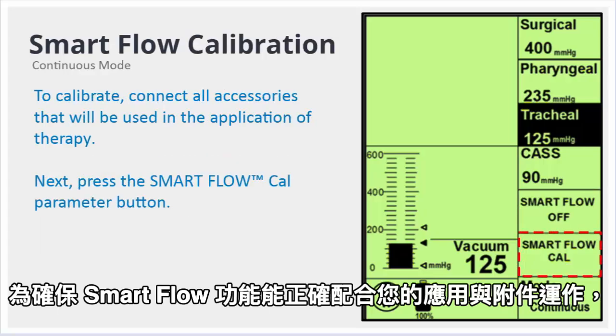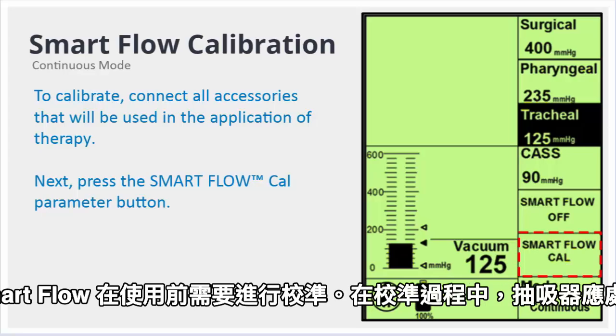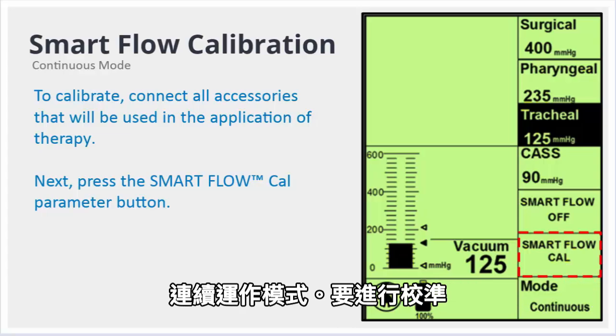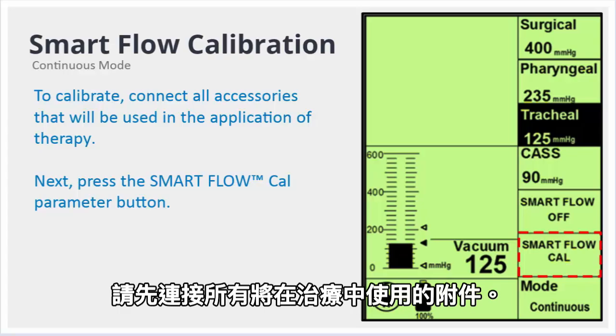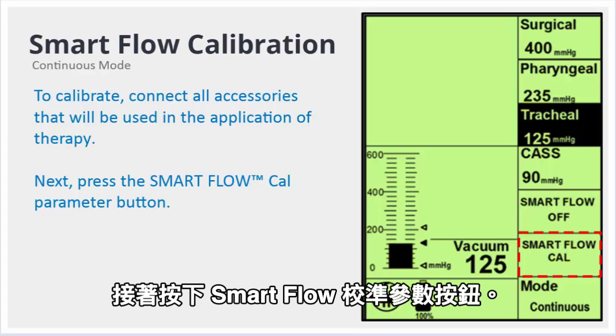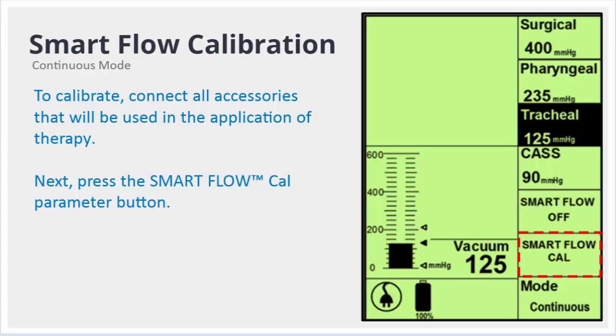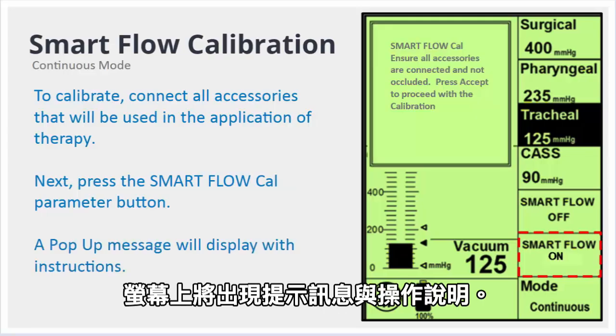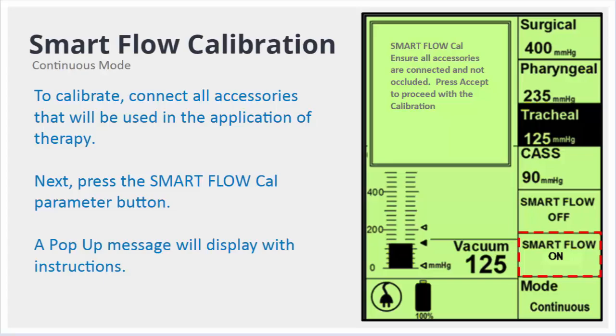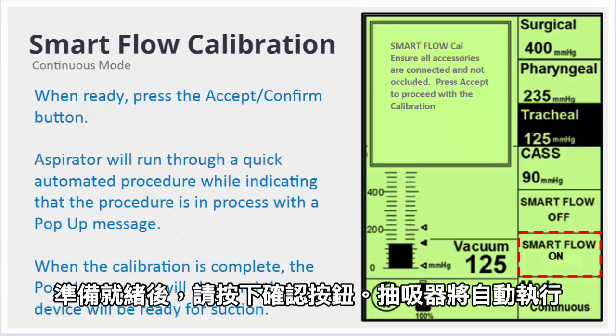To ensure that the Smart Flow feature works properly for your application and accessory package, Smart Flow needs calibration. During calibration, the aspirator should be in the continuous mode operational state. To calibrate, connect all accessories that will be used in the application of therapy. Next, press the Smart Flow Cal parameter button. A pop-up message will display with instructions. When ready, press the Accept Confirm button.